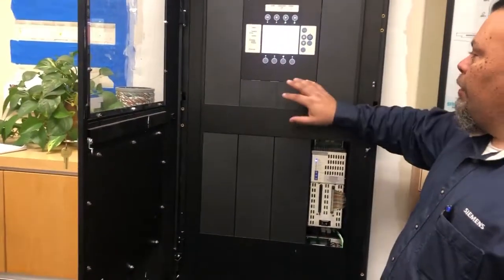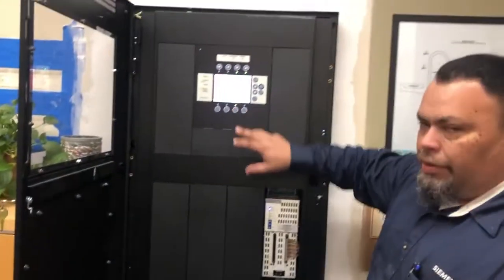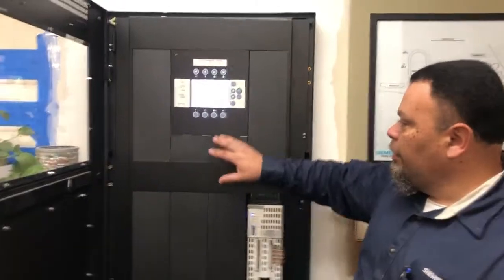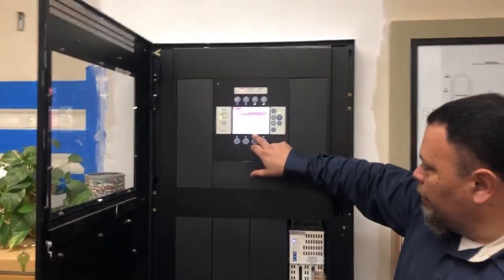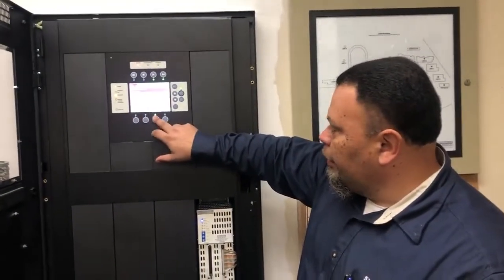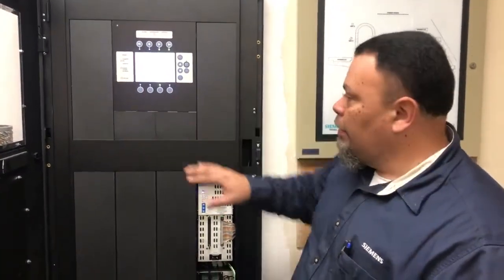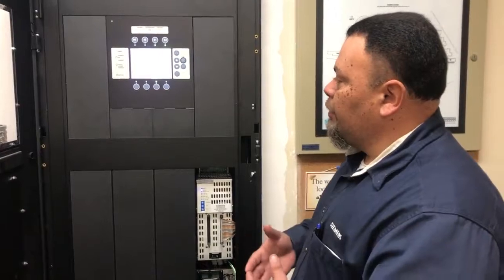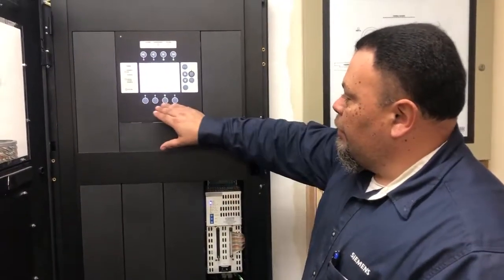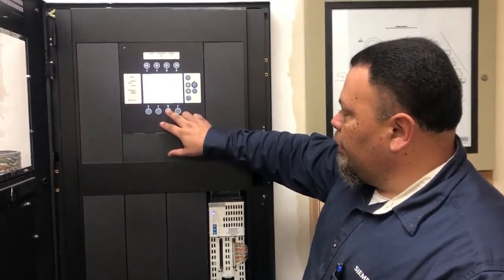Anything that you can interact with on the panel will be illuminated here. For example, unsilence audibles is an option that we can do at this point, and it's letting you know that by not being grayed out and having an LED on. When an alarm first comes in, you have to do things in order, and you're going to follow these LEDs to guide you through the procedures.